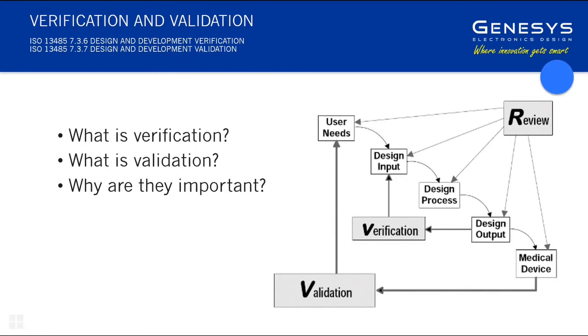Because this can really confuse people. So in the ideal world, you think, well, what's the difference? Well, quite significantly. Firstly, the specification might not be perfect, but verification certainly is a very technical activity, in terms of do the engineers confirm that what the engineer said the thing should do, it does. But from the user's point of view, it's a completely different mindset. Used in a clinical setting, particularly in an operating theatre or an intensive care unit, a high-stress environment with lots happening, the needs of the users of the device doing what it needs to do is much more than just the technical. It takes into account the usability and the functions and reliability, and a whole heap of other parameters.